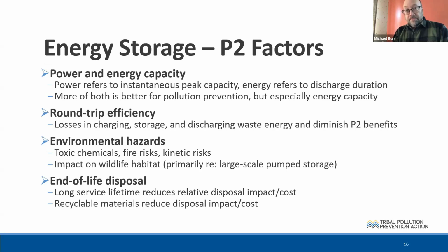Energy is a duration that work can get done. So you could have a 100 kilowatt battery that can put out 100 kilowatts instantaneously, but maybe it can only do it for 15 minutes. So that's a 25 kilowatt hour battery. Just a really easy way to think about it: it's 100 kilowatts, and if it's only 15 minutes, that's a quarter of an hour. So a quarter of 100 is 25.